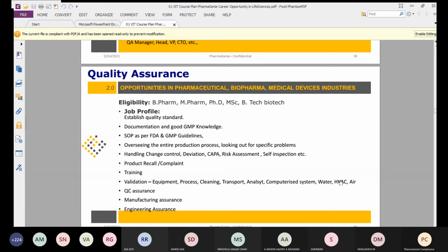Okay, HVAC. What is HVAC? Heating, ventilation, and air conditioning. To make the environment suitable for working, we should have air conditioning and a temperature and RH balance, which means relative humidity. If there is more moisture content in the area, the product will attract the water and the powder will become like a cake, which means the area has more RH. That impacts your product quality. So the area is always maintained at the intended temperature and RH. Why do I say intended? It depends on the product. There is no fixed temperature for every product. Of course, room temperature at 20 to 25 is fixed for 90% of products, but in some cases there will be changes and requirements in the process, because of product development complexity.